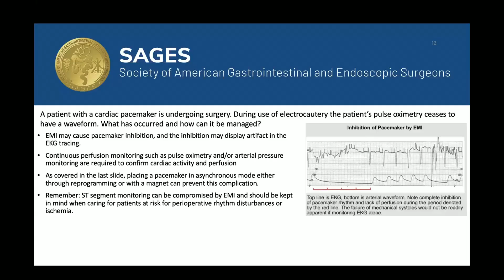All right, thank you, Dr. Weithorn. That was an excellent presentation on implantable devices. Yeah, it's very important to note where your electrical current path is, meaning if your dispersive electrode and your bovie, where you're using the bovie, there's a path between those two. You don't want any implantable medical devices close to that path. You want the ICDs and the pacemakers as far away from the path as possible.